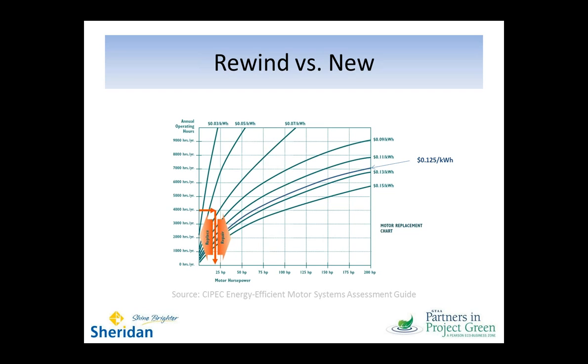And this curve that you see here is one that you'll find in a variety of reference sources, and it's built out of life cycle economic considerations. So it's looking at things like the cost to repair versus the cost to replace, the efficiency of a repair, the energy cost in the local region, and so on. The way you start using this curve is you start by drawing a horizontal line at your number of operating hours per year. So in this case, say we picked 4,000 hours per year, and we move horizontally out from that and drag it out to the intersection of the nearest cost curve.